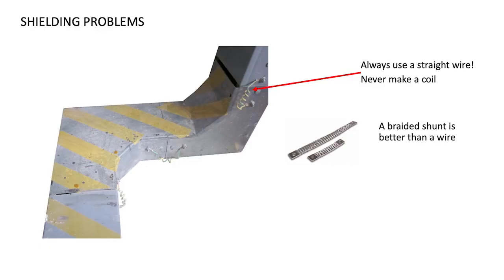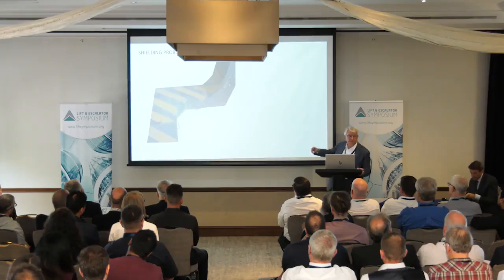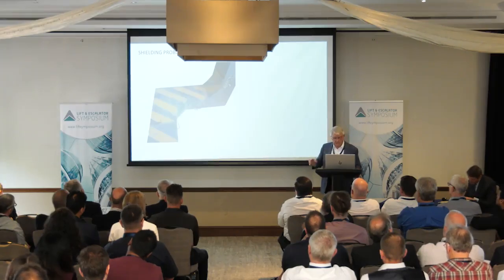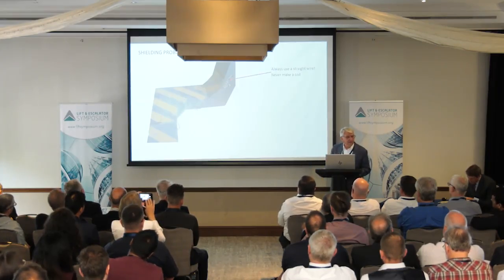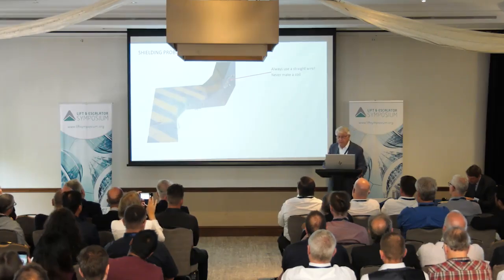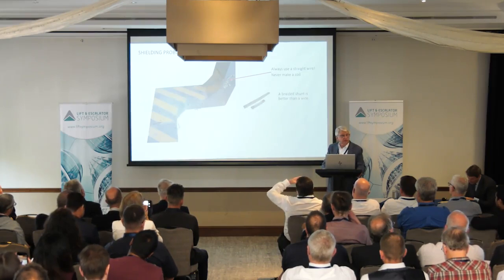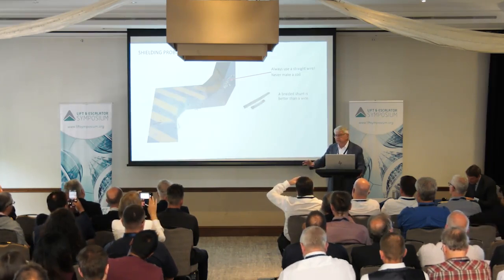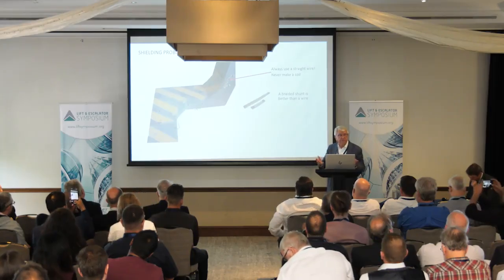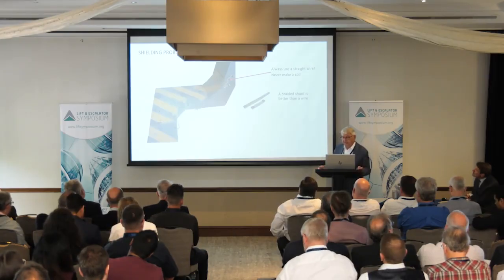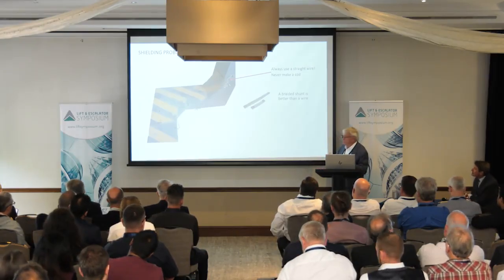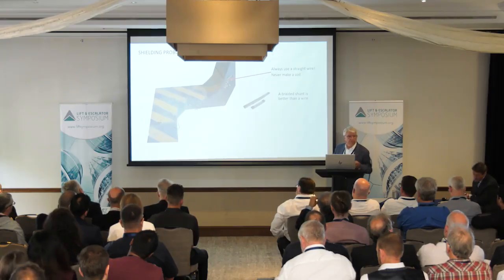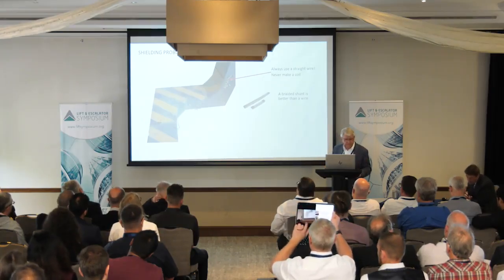So here's an installation of troughing in a machine room, and they put these little twisted wires between the segments of the troughing. Well, from a continuity perspective, it's good, but what those are is coils. And so never make a coil, because then you now have an inductor, and it's a little bit different. What really works better, if you're going to do that, is a braided shunt, because again, it has a lot more surface area. With all the little wires, the overall surface is much larger, and it gives you a good solid connection. Also, the couplings where the parts are screwed together need to be as good as you can make them, because all of this makes it a better earth device.